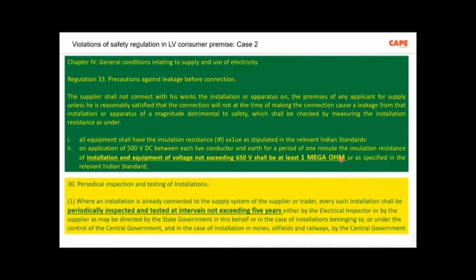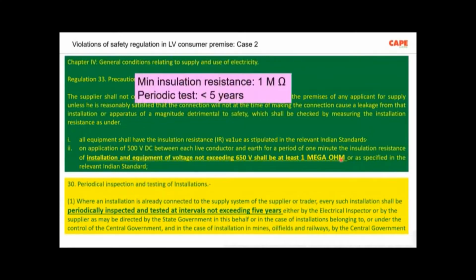I am explaining this because at the last part of the presentation I will show you a product which is sold in the market which actually violates this requirement. Also, Regulation 30 says every 5 years the power supply company is supposed to do this particular testing and ensure that the insulation resistance is higher than 1 mega ohm. If the insulation resistance is higher than 1 mega ohm, the chance of accidents is quite less.